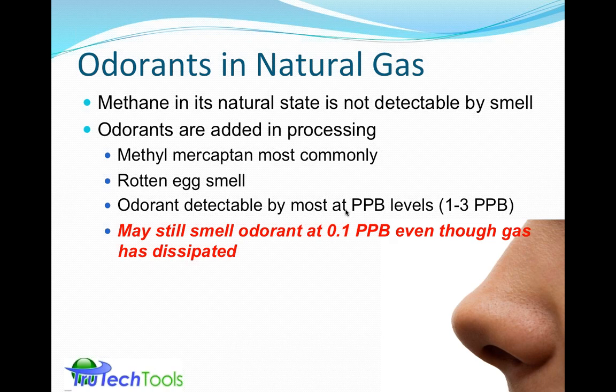And the odorant is detectable by most people at parts per billion level, very, very low level, has a really strong reaction. So 1 to 3 parts per billion is usually enough to allow someone to detect that. So the addition of a little bit of odorant to the gas stream allows it to be detected by most noses. Now, odorant can still be detected at 0.1 parts per billion. The odorant can be sticky enough or present in the air to give you the idea that there still is a gas leak present, even though the gas is dissipated.